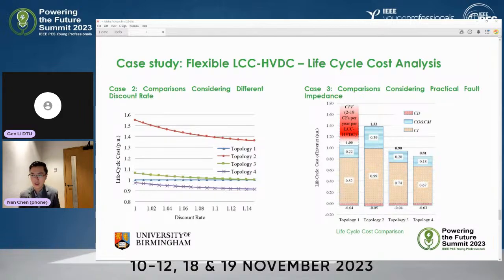For scenario 3, comparisons considering the practical fault impedance, we propose it because from studies by other researchers, we found that the average fault impedance from the fault point to the ground is not 0, but normally around several ohms. Our previous comparisons were based on a fault impedance of 0 ohms, but here we put this data into the comparison. From this, we can find that the proposed topology 3 and topology 4 can reduce the life cycle cost by 10% and 19% respectively.